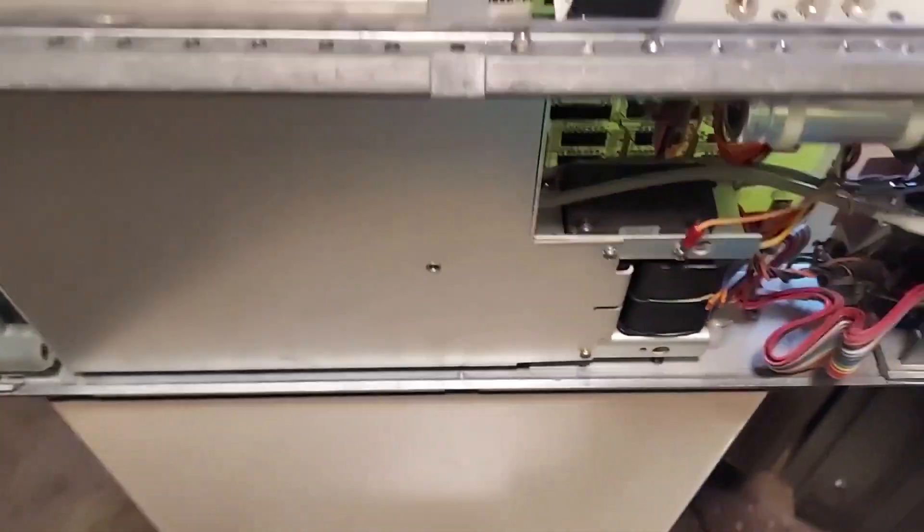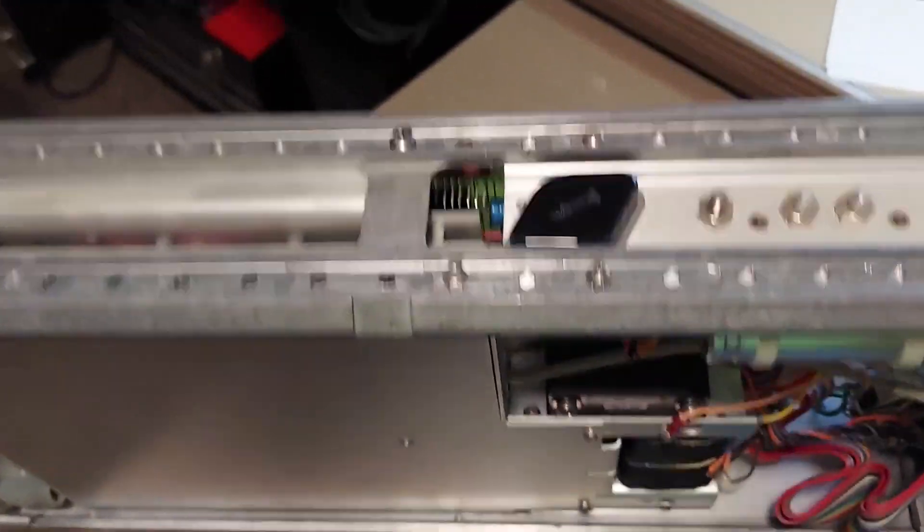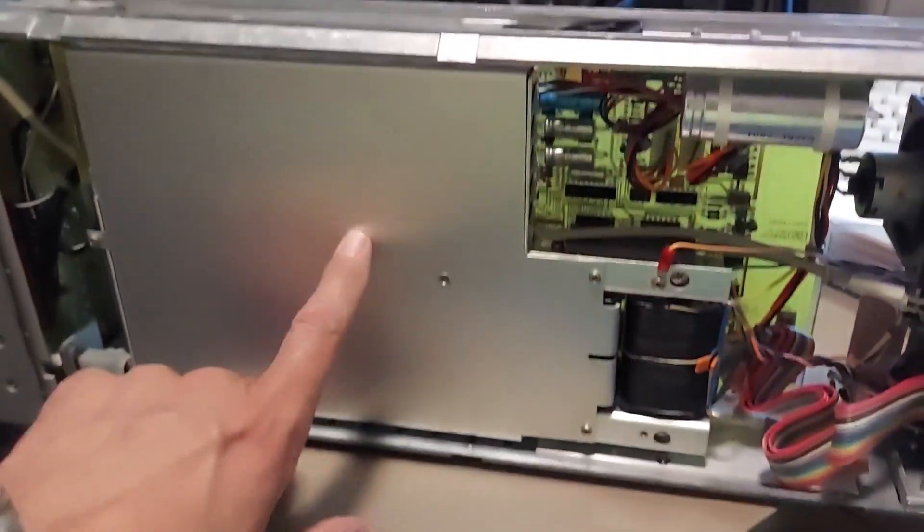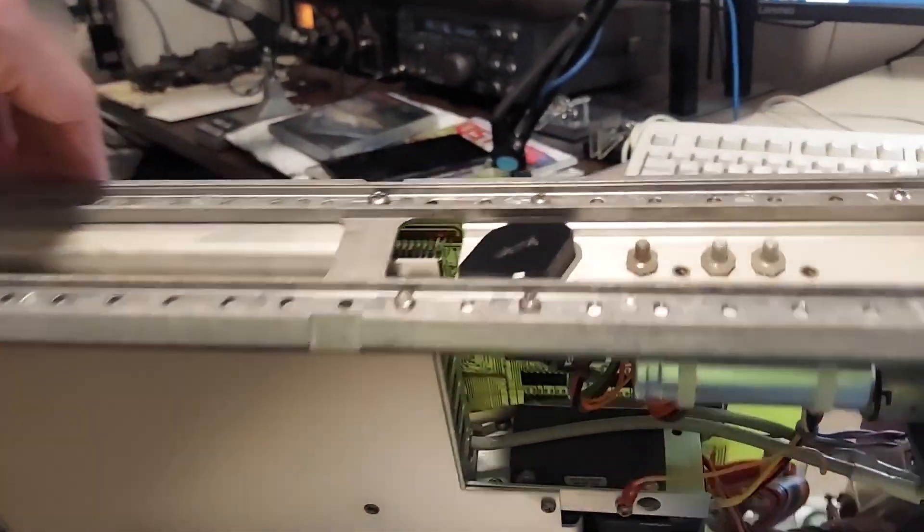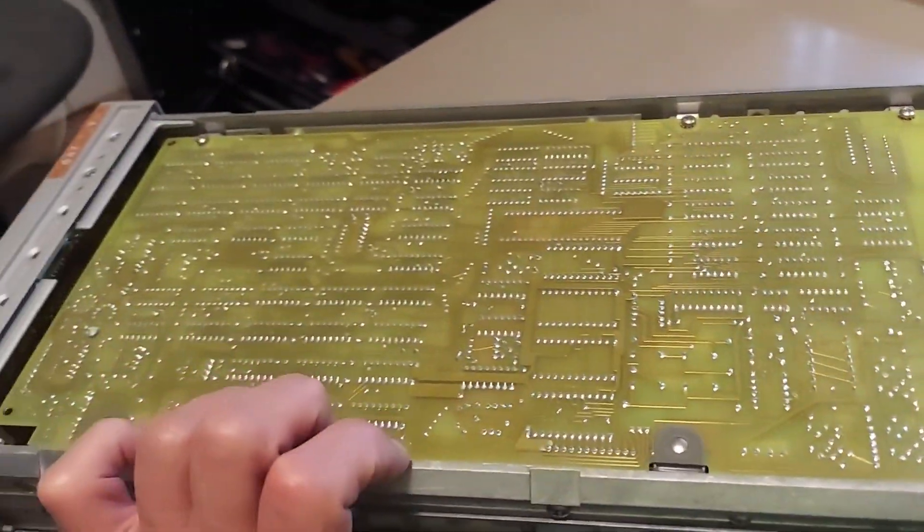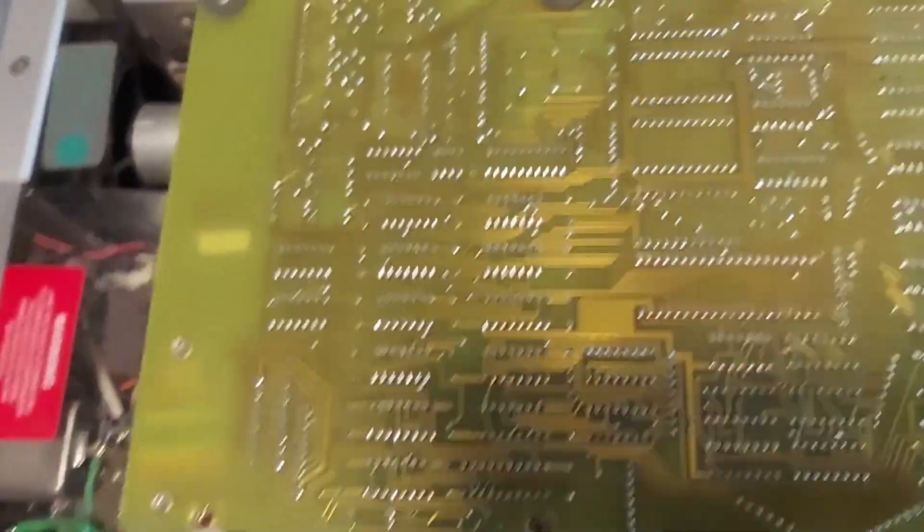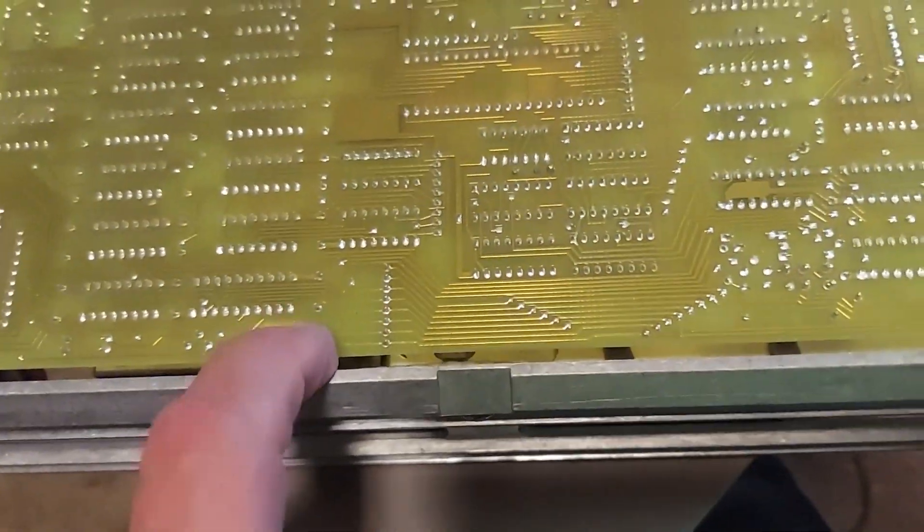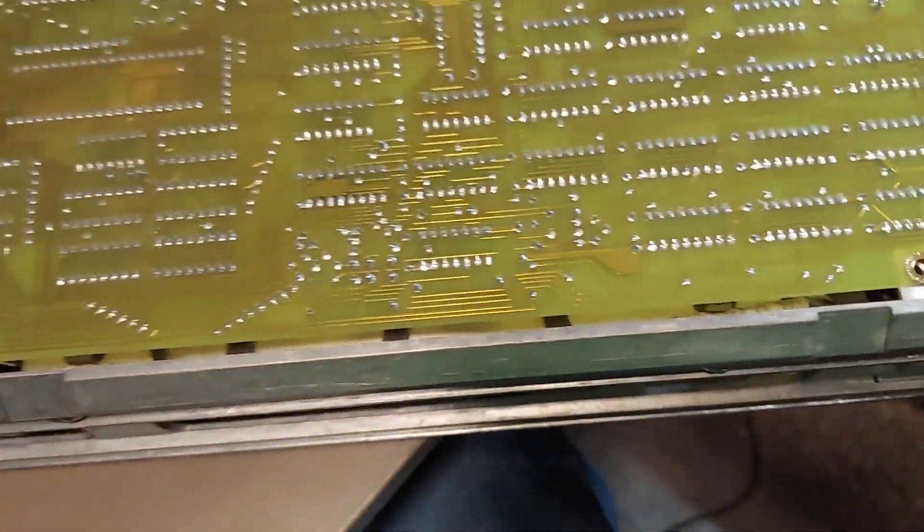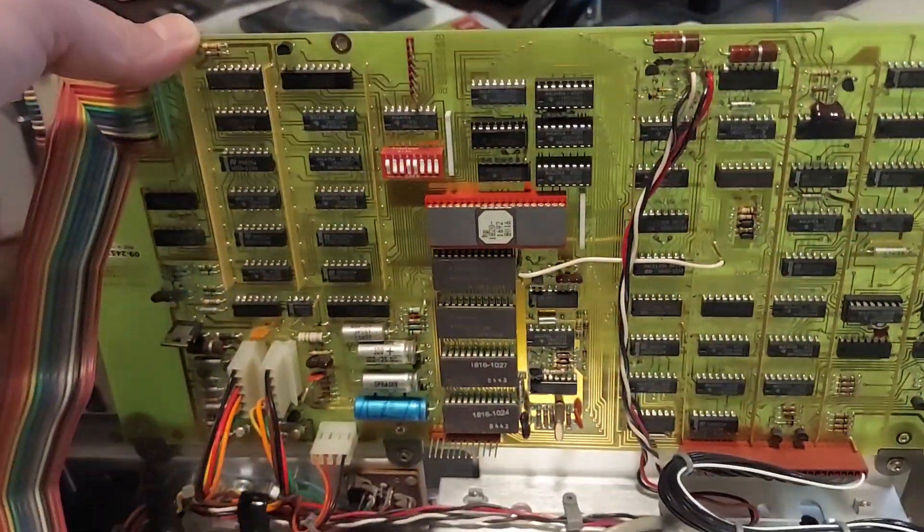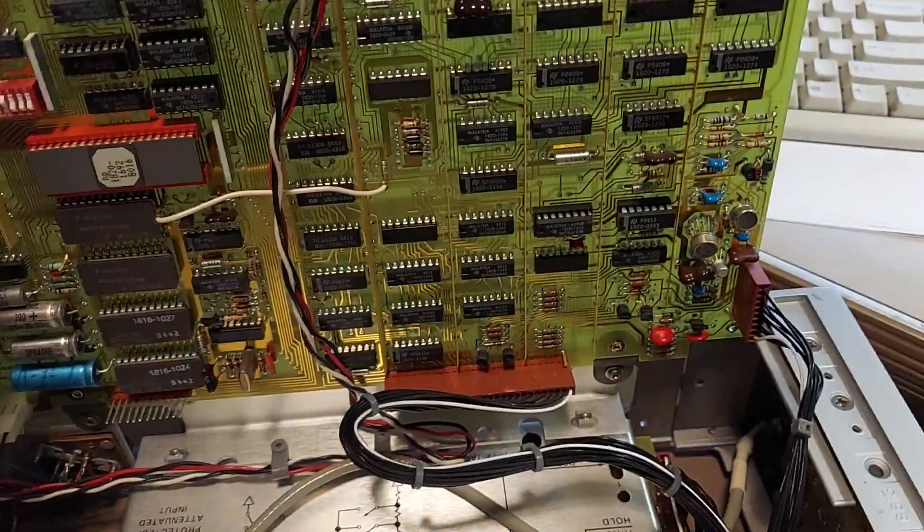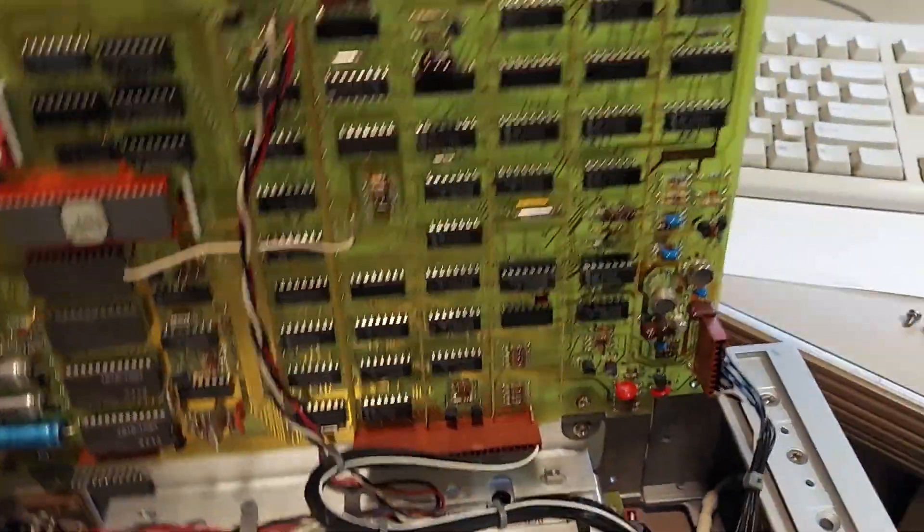All right, so now we have to take the both the top and the bottom's off, and the side rails off each side. And here is the analog board, which our suspected trouble is. And then the logic board is on this side here. Nicely constructed, nice HP construction quality, so let's keep digging. Okay, to get the logic board loose, you have to take that screw loose, a screw here, and a screw here, and now this board just folds right open. Everything's easy to get to, and HPIB settings are here. And everything's just nice.